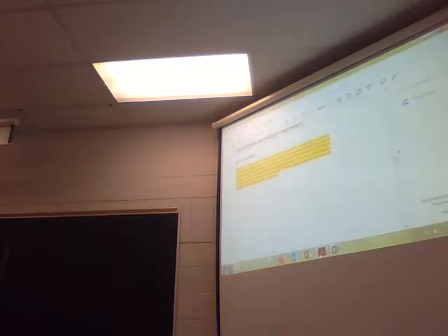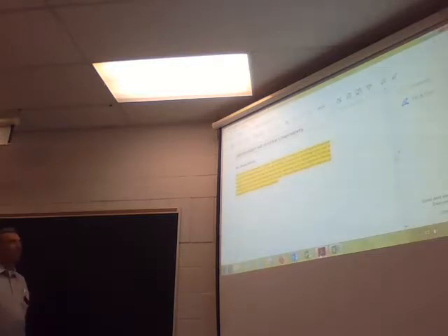Instrumentation air, system components, compressor, that's always good. You want to have compressed air, it's always good to have a compressor. The type of compressor chosen, reciprocating, rotary, centrifugal, depend on the load requirements of the air system, compressor operating costs, and if the air compressor is oil free or not. If the air compressor is to be oil lubricated, then an elaborate and thus expensive filtering system must be used to ensure oil-free air.